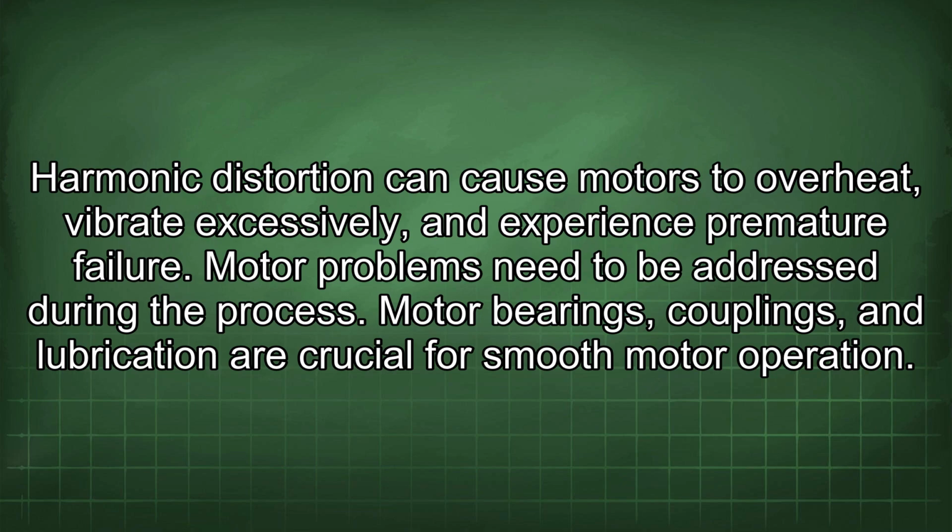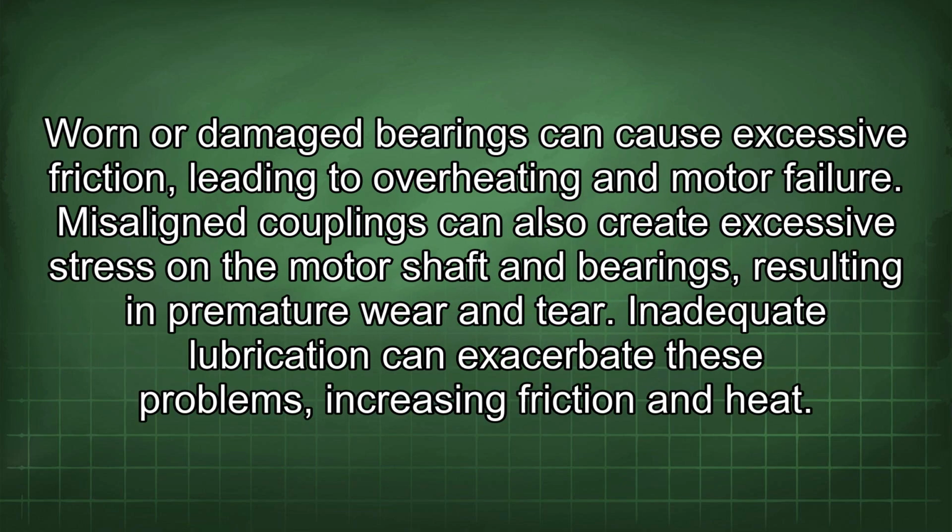Motor bearings, couplings, and lubrication are crucial for smooth motor operation. Worn or damaged bearings can cause excessive friction, leading to overheating and motor failure. Misaligned couplings can also create excessive stress on the motor shaft and bearings, resulting in premature wear and tear. Inadequate lubrication can exacerbate these problems, increasing friction and heat.